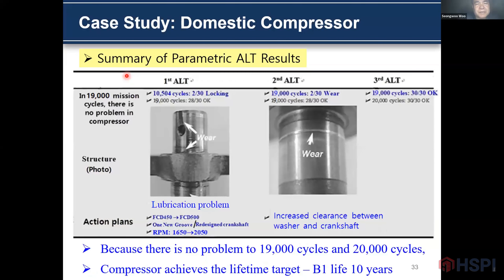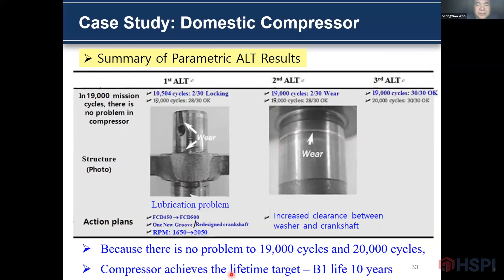This is a summary of the parametric ALT results. In the initial test there was no problem at 19,000 cycles. In the first parametric ALT, we found a lubrication problem. In the second ALT, we found wear on the surface of the crankshaft. In the third ALT, there was no problem at 19,000 and 20,000 cycles. The compressor achieved its life target beyond 10 years.